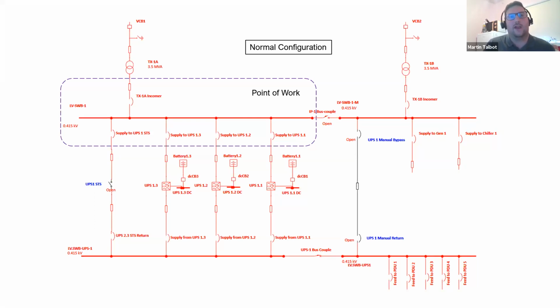MV or HV equipment might have an AFLR rating. It's sort of unusual for LV to be type tested to that degree. Okay, similar to what Marcin said, we've got a 3 UPS parallel system, a redundant system, with an input and output board configuration, manual bypass and static bypass. And this is our point of work that we want to safely isolate to shut down and clean, but maintain supplies through the manual bypass for the customer.